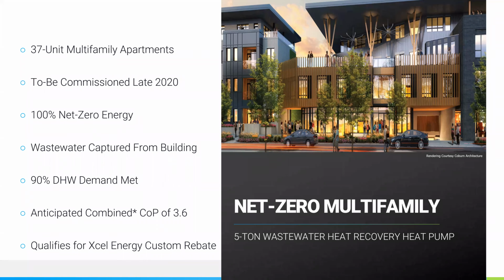Putting that into perspective, 3.6 is about 360% energy efficient. How do you get there? For every 1 unit of electricity we're putting in, we're getting out 3.6 units of heat energy to the domestic hot water loop. Our device makes the incoming energy more efficient through the heat pump refrigeration process. Compare that to electric resistance, which has a COP of about 1, or even the best natural gas condensing water heater or furnace, at a COP of about 0.95. The efficiency gain with this type of system is huge.